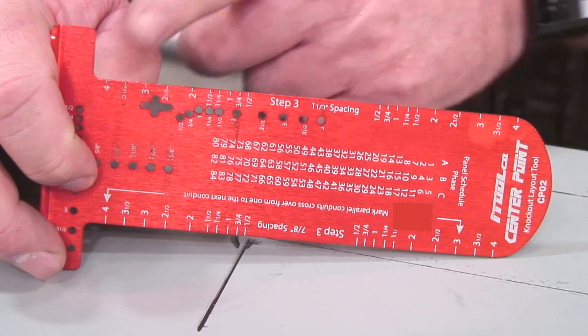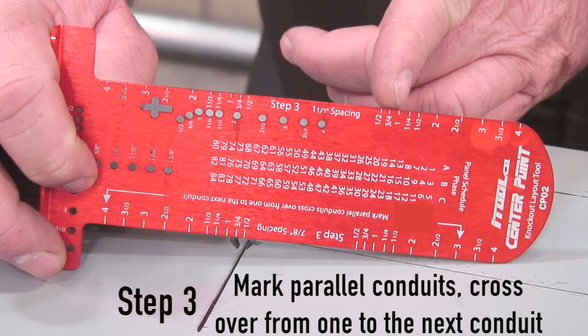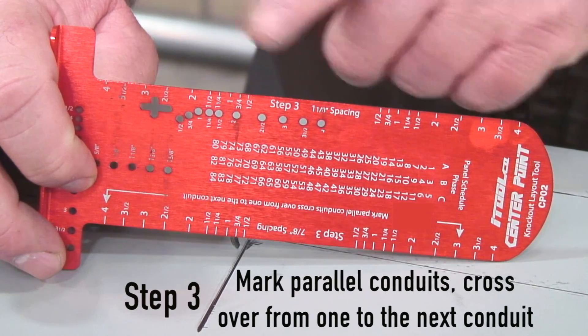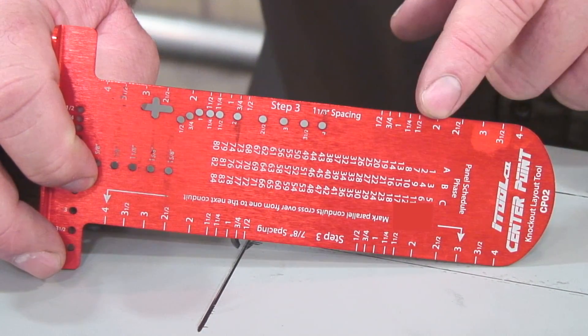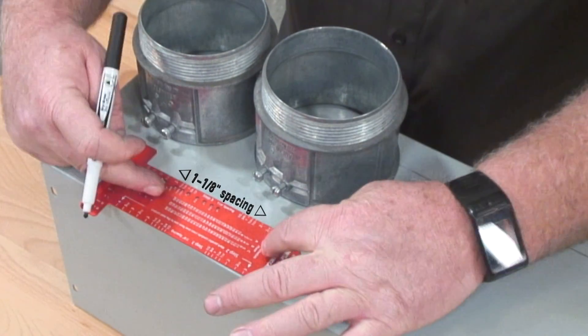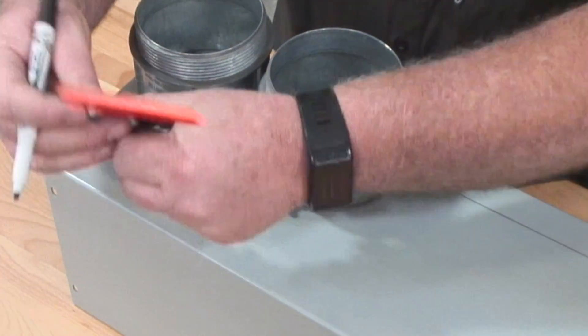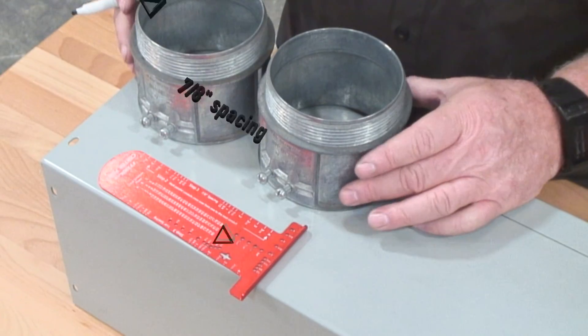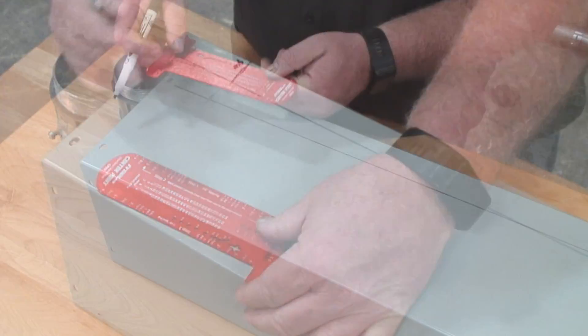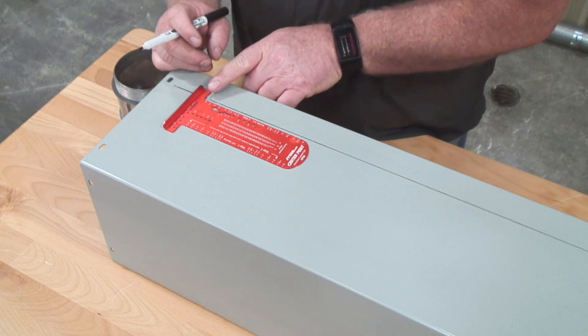Moving now to step 3 — we are going to be positioning the conduits apart from each other. From a 2-inch to a 3-inch, you'll see all of your trade size conduits, that's just one size to the next size. Using this side of the CenterPoint tool, you have 1-1/8ths spacing, which is going to give you an inch and an eighth between your conduits. Flipping the CenterPoint over gives you tighter spacing — 7/8ths spacing between your conduits.